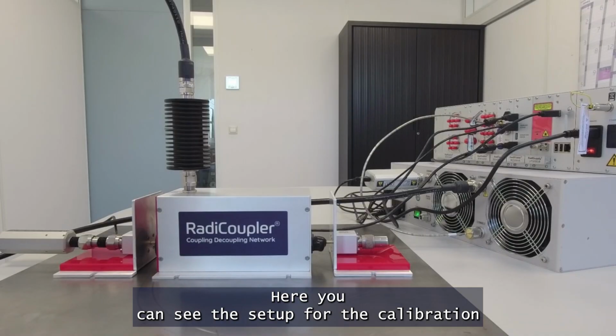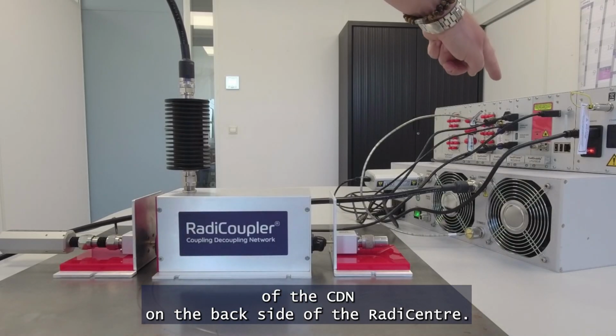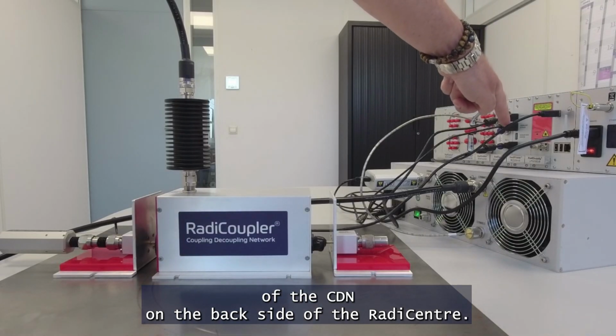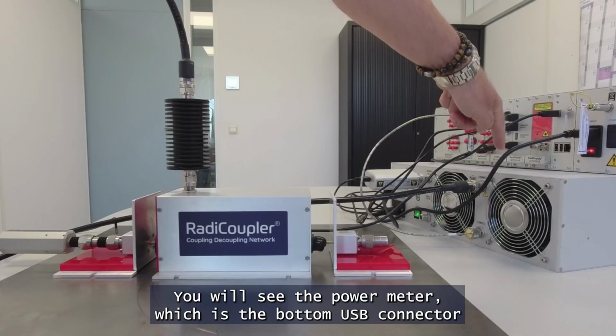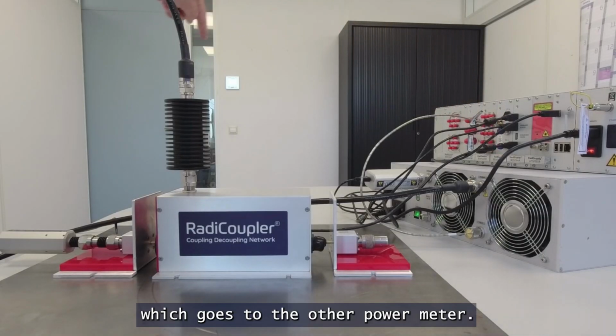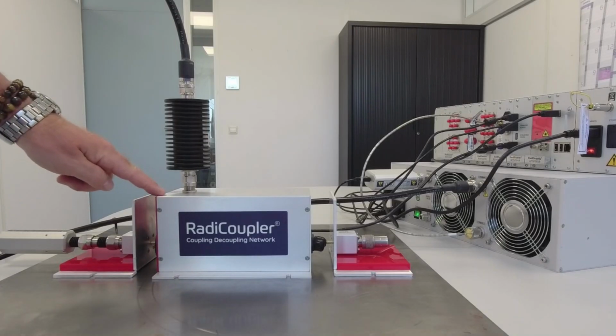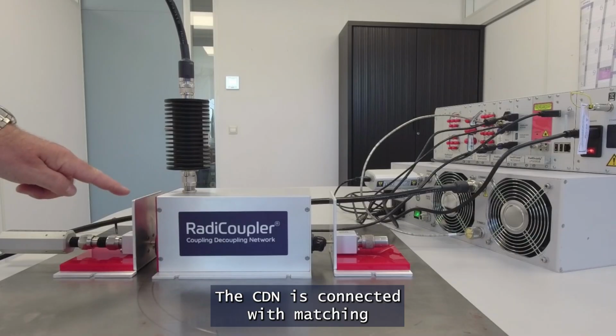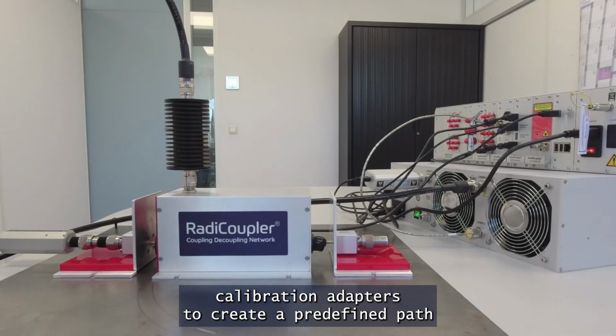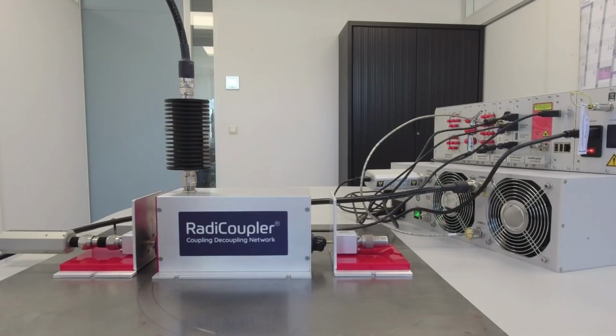Here, you can see the setup for the calibration of the CDN. On the back side of the RadiCentre, you will see the power meter, which is the bottom USB connector, which goes to the other power meter. The CDN is connected with matching calibration adapters to create a predefined path.